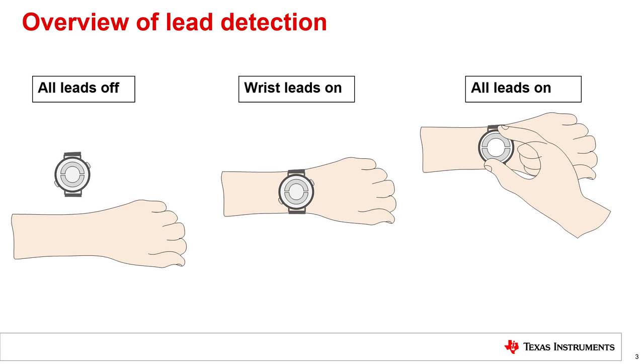Let us consider a wrist-borne wearable device that has electrodes for ECG signal acquisition. Here we consider a case where two of the electrodes on the bottom face of the watch make contact with the left wrist of the user when the watch is worn. We call these the LA, or left arm, and RLD, or right leg drive electrodes. Whenever the ECG signal needs to be acquired, the user touches an electrode on the top face of the watch. We refer to this as the RA, or right arm electrode.